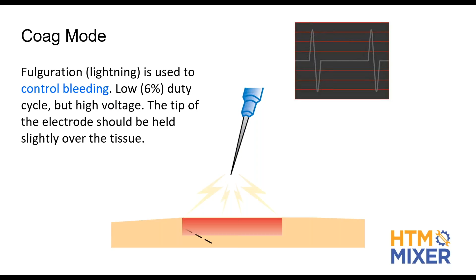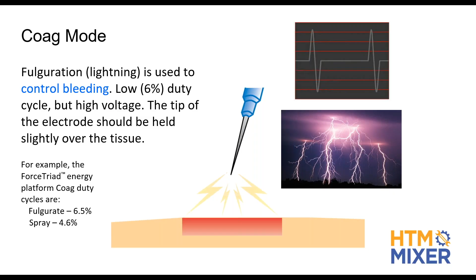And if we look at the ForceTriad, I used that one because that's one of the ones we teach. The fulgurate is 6.5%. The spray is even lower than that, which means that the waveform is going to be higher. The lower the duty cycle, the higher the waveform. Then I compare this. When they call that lightning, fulguration, that's exactly the same. If you're out on a golf course, looking for the path of least resistance, it's probably the golfer. That's shocking.